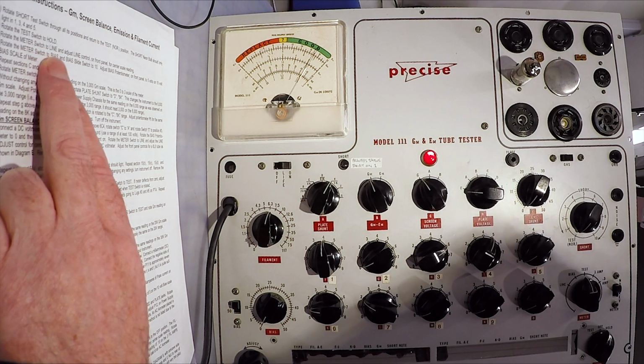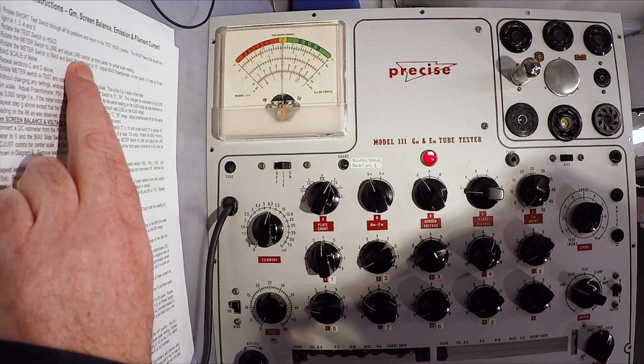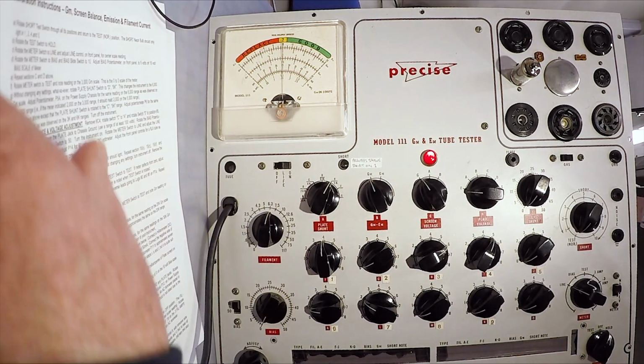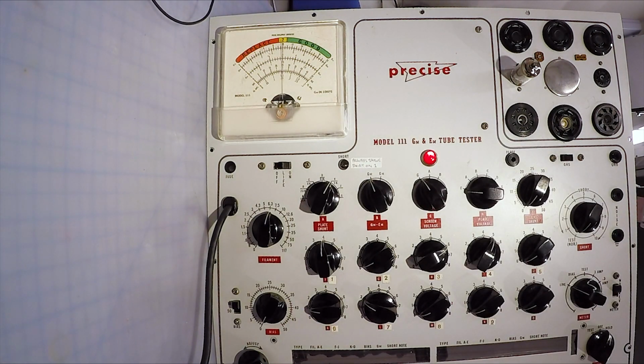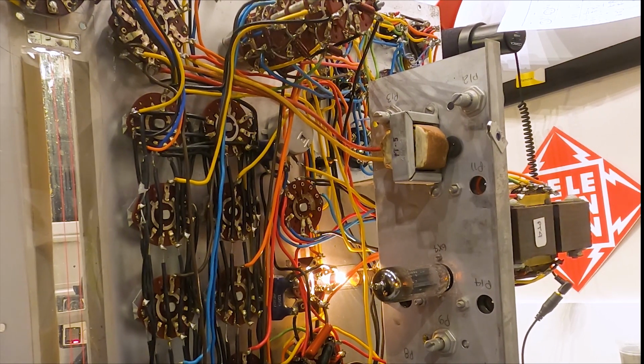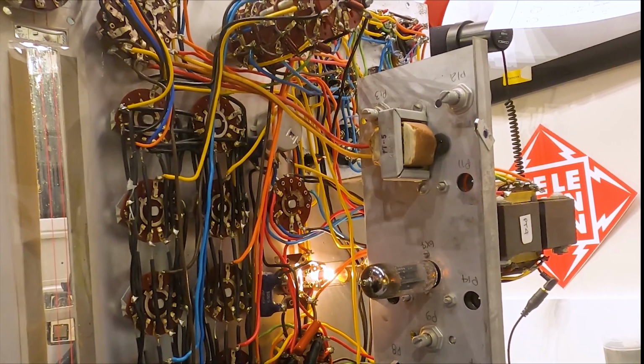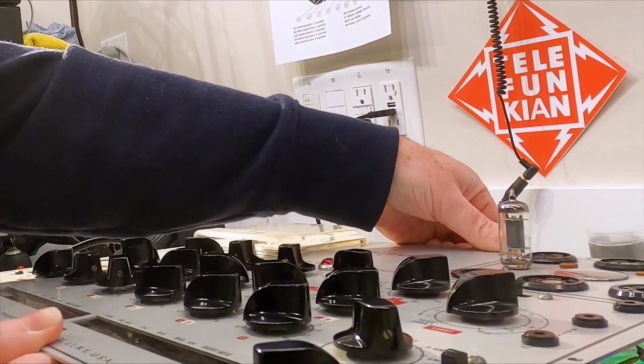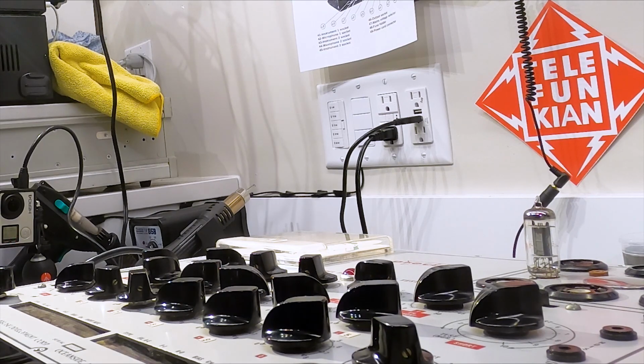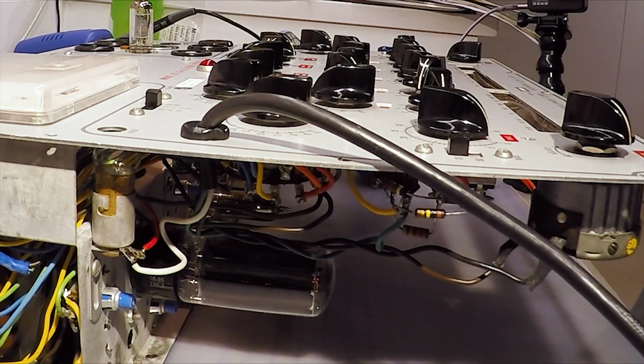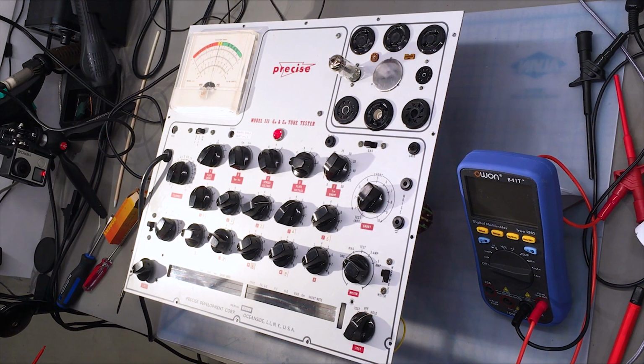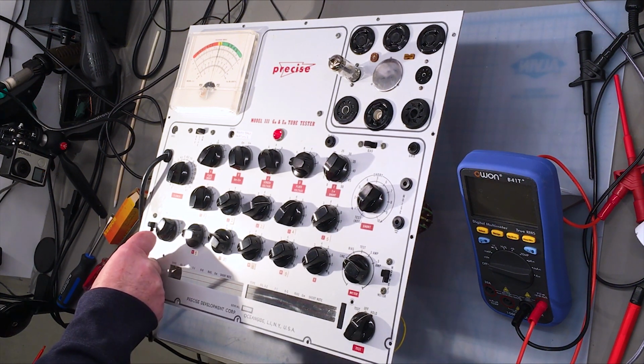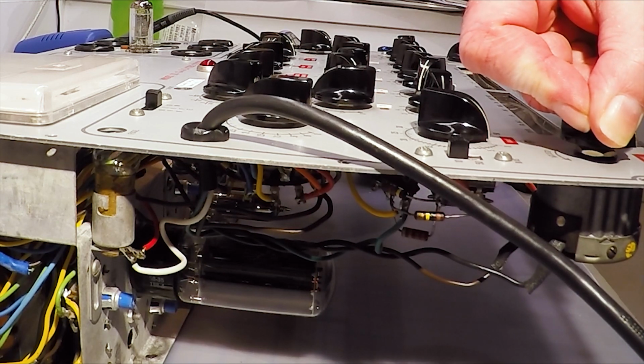We now rotate the test switch to hold, and we rotate the meter switch to line and adjust the line control for a center scale reading. Now, we're going to be making some adjustments that are going to be influenced considerably by the position of the meter, and accordingly, I'm going to tilt the tester on its side, or rather on its back. And this way we get appropriate parallax on the meter. So with the switch to line, we adjust the line so that we have center deflection on the meter, which we do have now.